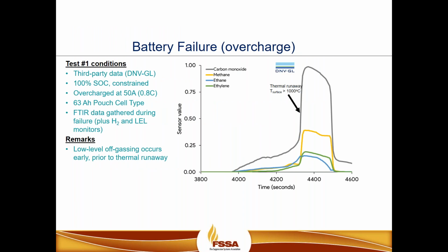So looking at some of the battery failures and the abuse factors, I wanted to show you some tests that were done through third parties. DNV did an extensive amount of testing and documented their tests. So I wanted to share with you some of the testing that they had done. This particular test is showing an overcharge electrical abuse factor, where they overcharged the battery at 50 amps. And the particular pouch or cell type used here was a 63 amp hour.